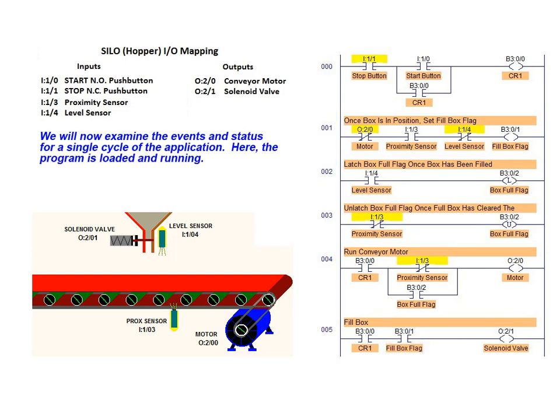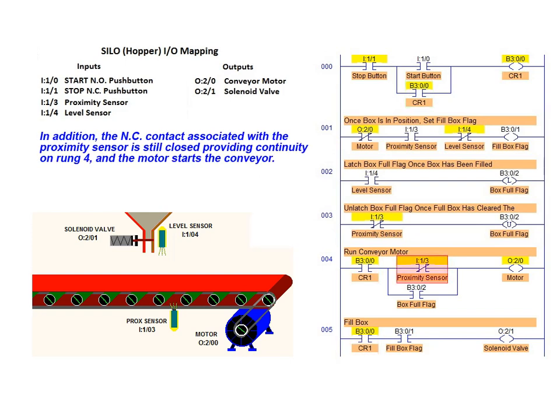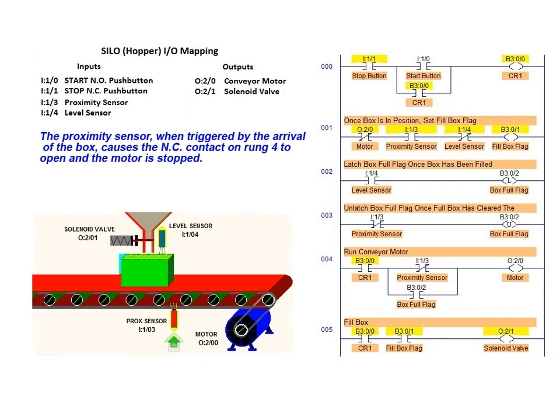We will now examine the events and status for a single cycle of the application. Here we have the program loaded and running. When the start button associated with input rack 1 bit 0 is pressed, the seal-in circuit locks up on rung 0, and the CR1 contacts on rungs 1, 4, and 5 close as they are associated with the B3 0.0 holding bit. The NC contact associated with the proximity sensor is still closed, providing continuity on rung 4 and the conveyor motor starts, bringing a box forward to the filling station. When triggered by the arrival of the box, the proximity sensor causes the NC contact on rung 4 to open, and thus the conveyor motor is stopped.